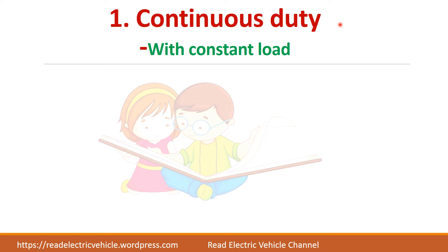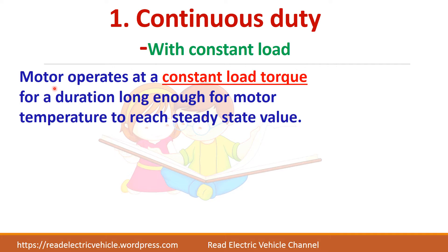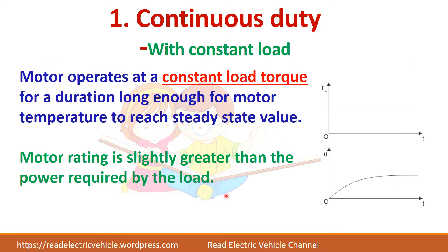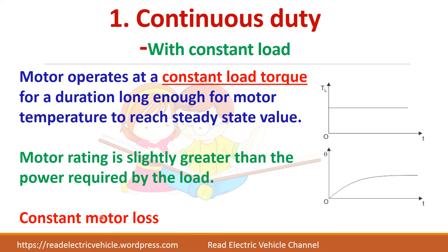First, we will see continuous duty with constant load. Here, the motor always operates with a constant load torque, such that the temperature rises and reaches the steady state value. In this case, the motor rating should be slightly greater than the power required by the load. Because if you choose a lower rating, your temperature may exceed and burnout may occur. So it is always better to choose a rating greater than the power required by the load. Since the load is constant, the losses will also be constant.